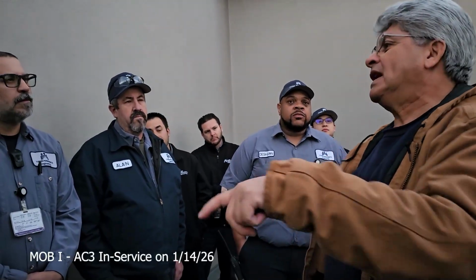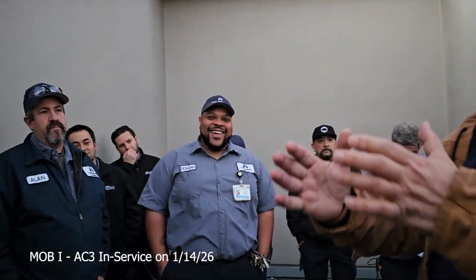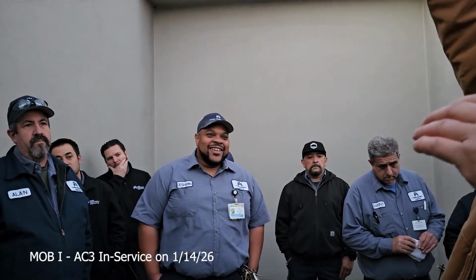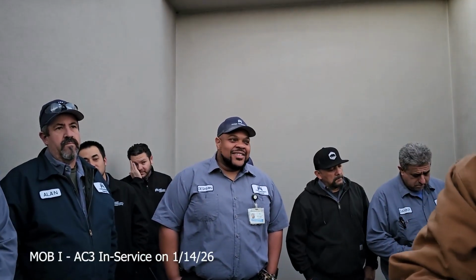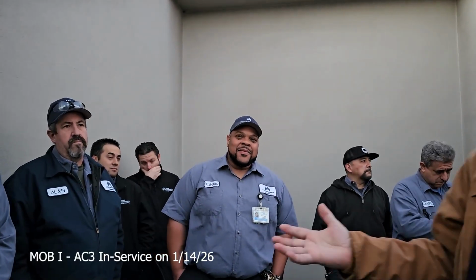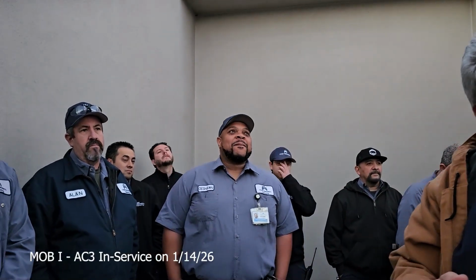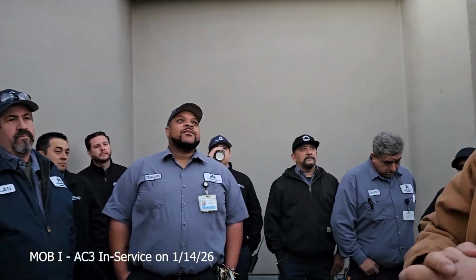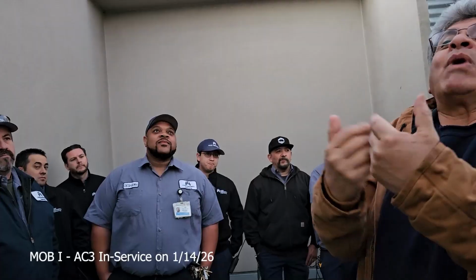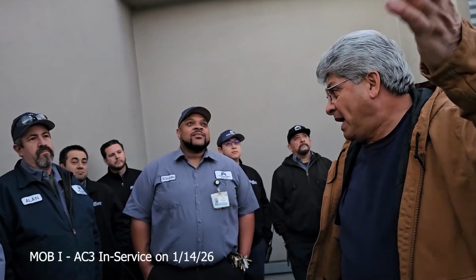Chad took us downstairs to your engineering room, and I saw your set point is 2 inches. You're running 1.96. Set point 2 inches? Yeah. Why so high? You got to remember, you got guys that are much more up in the food chain that make these decisions. When we build them, if they want 3 inches, I got a job in Tennessee, they want 5 inches of static. I don't ask why you need 5 inches. That's what we just built it for. Okay. So this machine will maintain 2 inches of static.